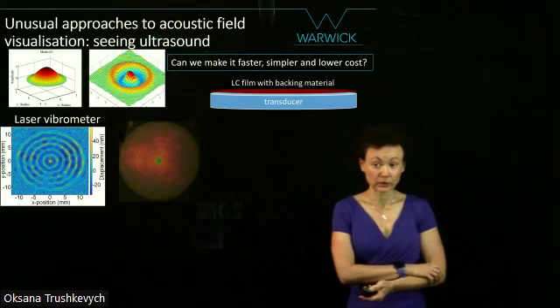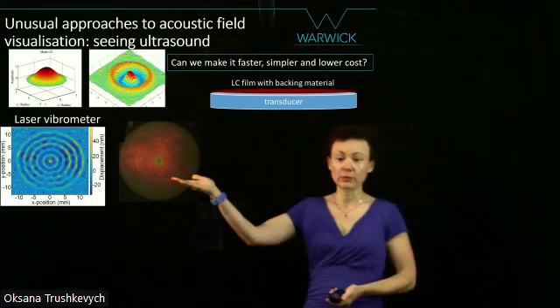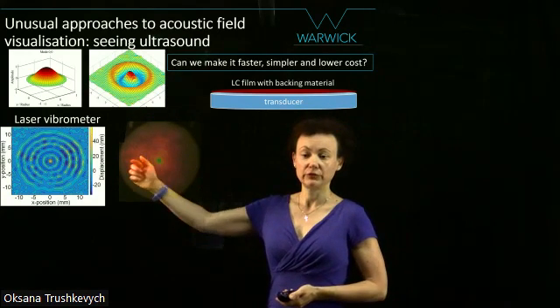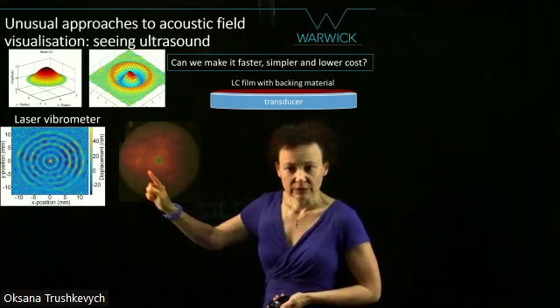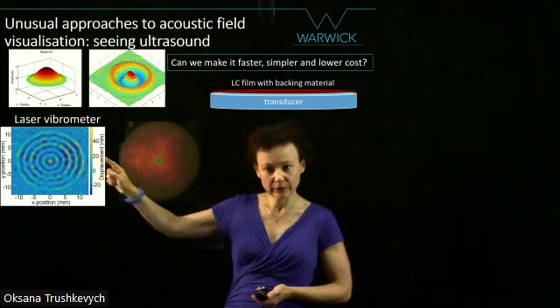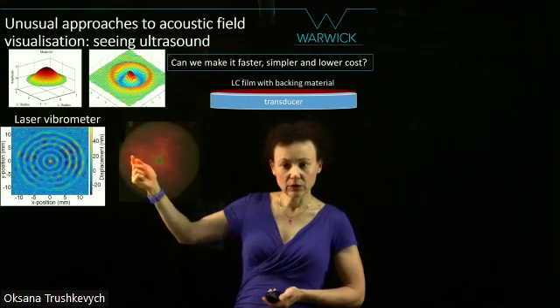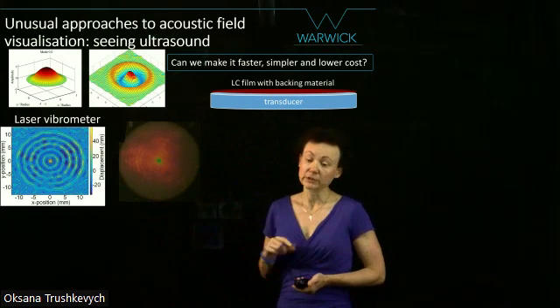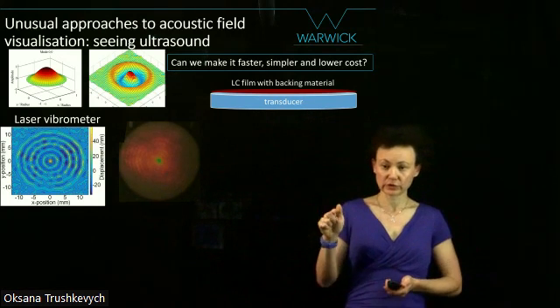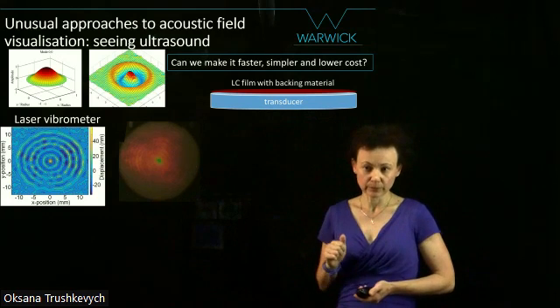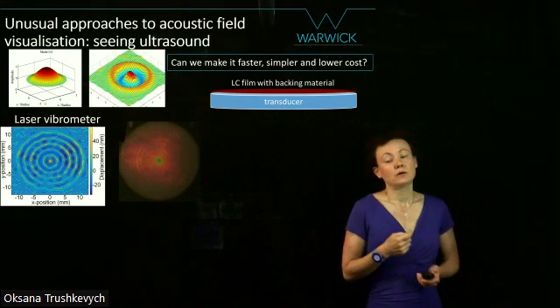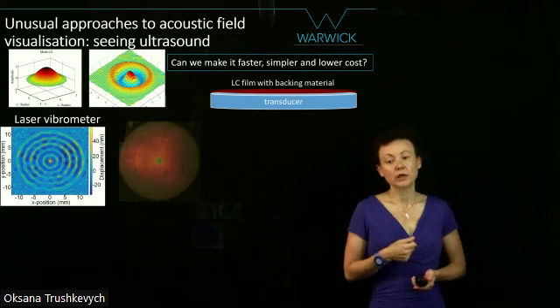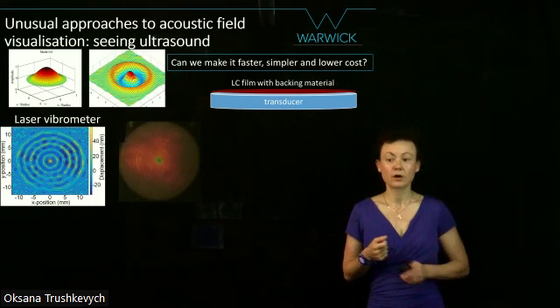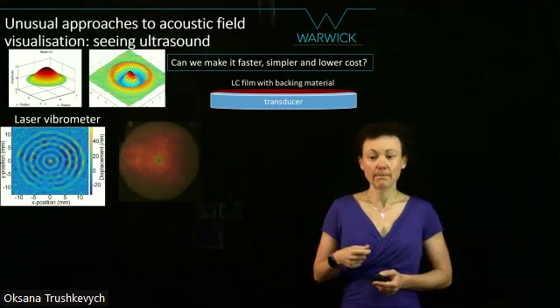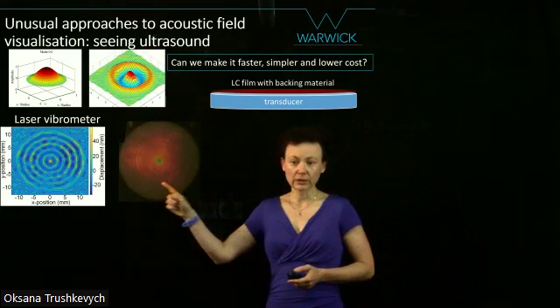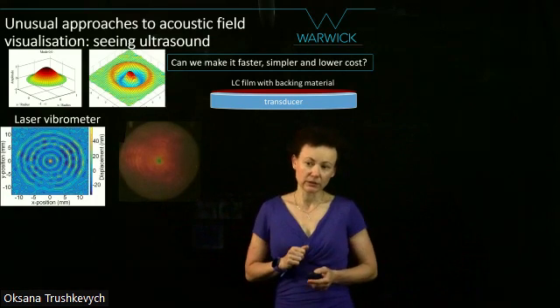Let's see whether that works. This is the same mode. This is 11-0 mode, but now it looks a bit different to the vibrometry picture. And that's because it only gives you maximum displacement. It will not give you phase. It will just give you areas that move up and down. What is happening here, we are absorbing energy, converting it to thermal and visualizing that. But we do it with sufficiently high resolution, we can see the detail.